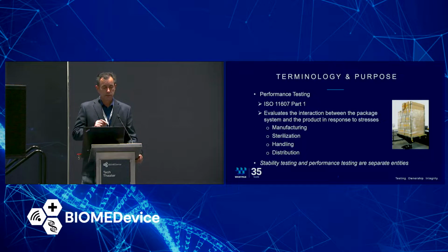So then, when we look at performance testing, as opposed to stability testing, we also look at the guidance document for terminally sterilized devices, ISO 11607, which evaluates the interaction of the package system and the product in response to stresses. Those stresses being manufacturing, sterilization, handling, and distribution. Now, you might think of the stresses in manufacturing, well, you're molding that very many components into a single device.